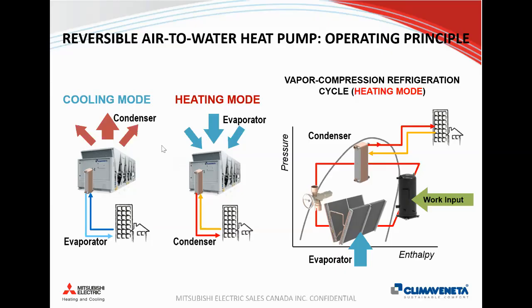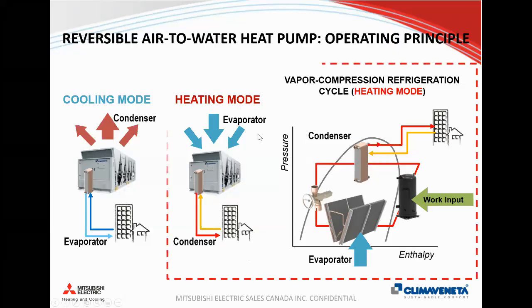So within the machine, there's a 4-way reversing valve, which redirects the flow of refrigerant. So if we look specifically at heating mode for a reversible heat pump, it's the same machine, but that coil that was previously being used as a condenser is now being used as an evaporator. So this means we're extracting heat from the ambient surroundings, and we're moving that heat into a hot water loop to use in our building.